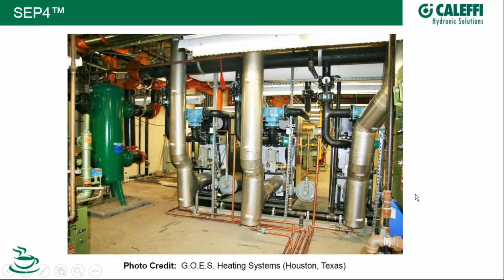Now you might say to yourself, these don't look like boilers that would need a hydraulic separator, because they look like non-condensing boilers, and if you said that, you probably have a pretty sharp eye. And you are correct. These 3 boilers are non-condensing boilers. They wouldn't be hurt by a hydraulic separator. They probably have less restriction in them than a condensing boiler, but you can tell they're non-condensing because they have these blue items here. These make sure that the return water back to the boiler stays above the temperature at which dangerous, destructive flue gas condensation can occur. So these are 3 thermostatic mixing valves that perform that function.